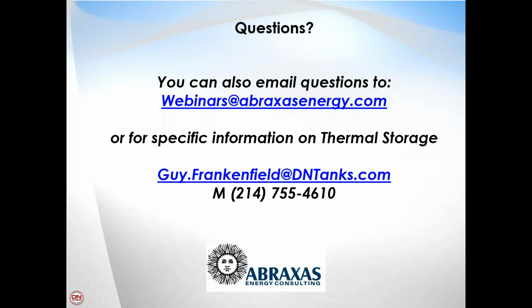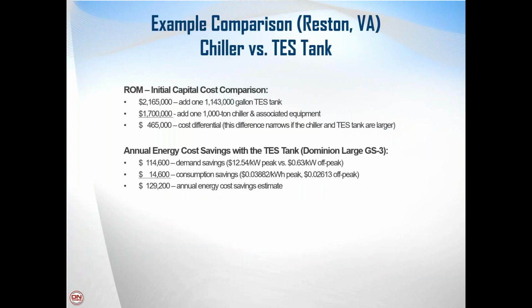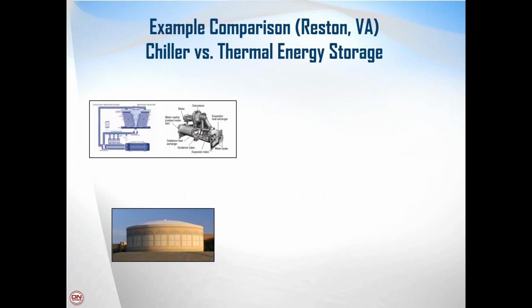Great. And then we did have another question here. Can you go more in depth on any maintenance that's required for these tanks? Sure, let's just look at a typical tank, what it looks like. For our tanks, you're looking at an example of one in the lower picture. There is no maintenance regarding the integrity or performance of the tank. There's no maintenance required because we build our tanks out of materials that will not degrade or corrode over time. All the metal components are encased in concrete. All the piping components are materials like PVC or FRP that will not corrode over time.